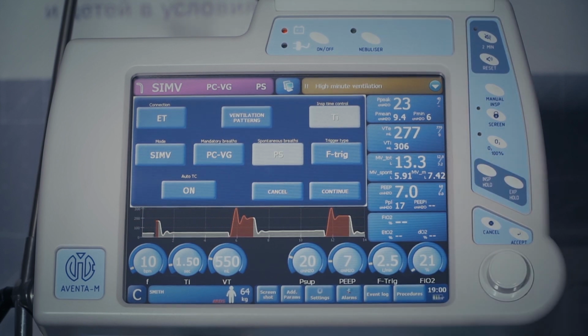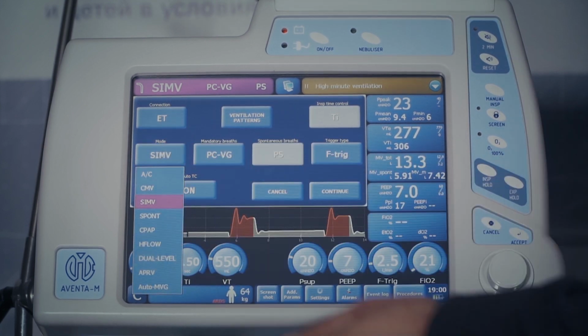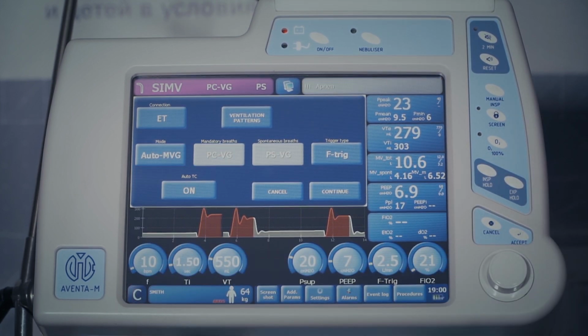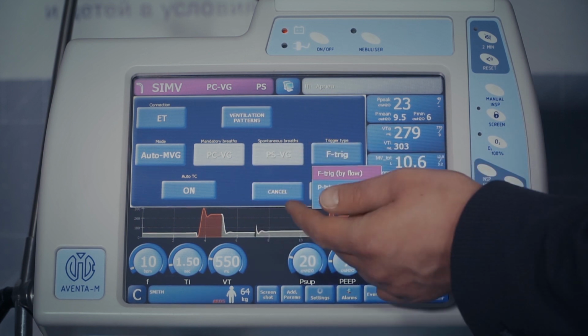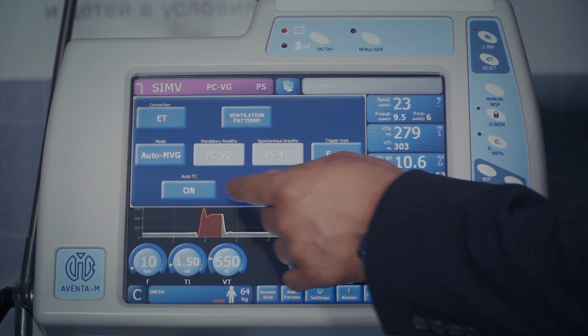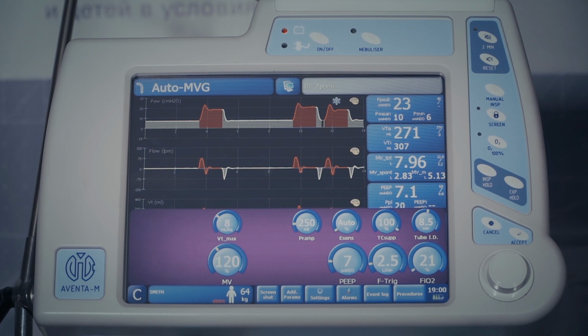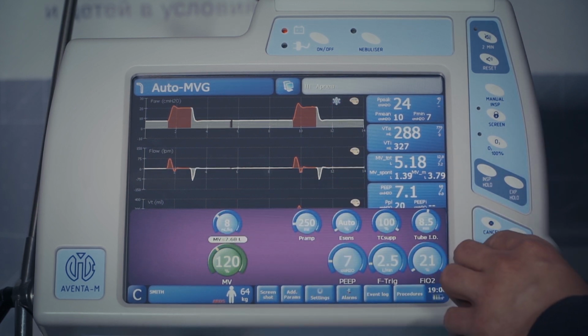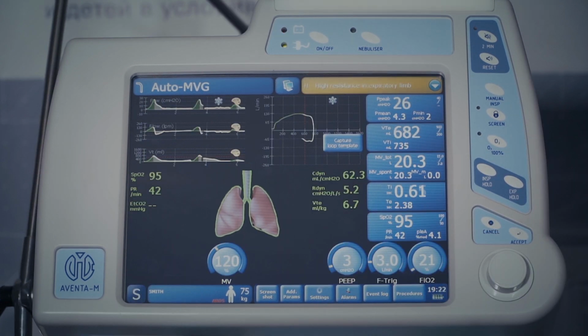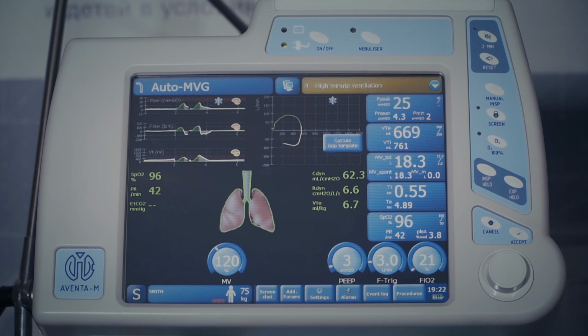Let's consider one of the most advanced ventilation modes, adaptive mode Auto-MVG. This mode supports adjustment of most of the controlled parameters, such as mandatory breath rate, respiratory volume, peak pressure, inspiratory time, etc., to changing respiratory mechanics and spontaneous activity of the patient. This mode is designed for achieving the preset minute ventilation volume at minimum possible load on the respiratory system, which ensures comfort to a patient.